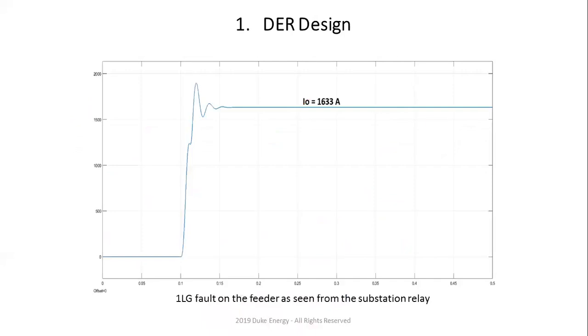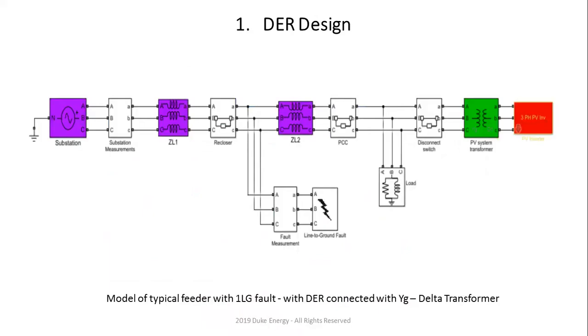And when I simulated the fault at the head of the feeder, what I noticed is that a 1633 amps fault is seen. And you have positive, negative, and zero sequence current, so they're all the same for the line to ground current, right? And then I added the PV system at the end, and I tied it through a transformer. Typically, PV systems have transformers on the AC side. Somewhere I have seen them as low as 315 volts, and I have seen them as high as 480 volts.